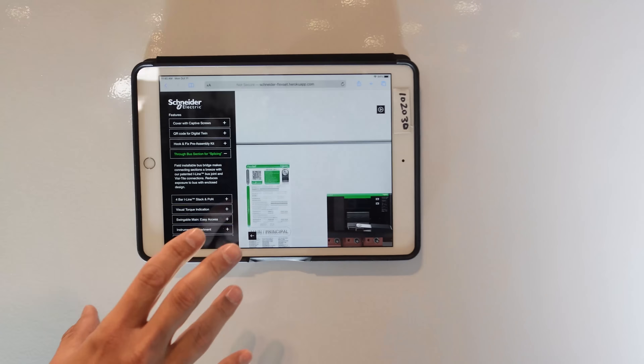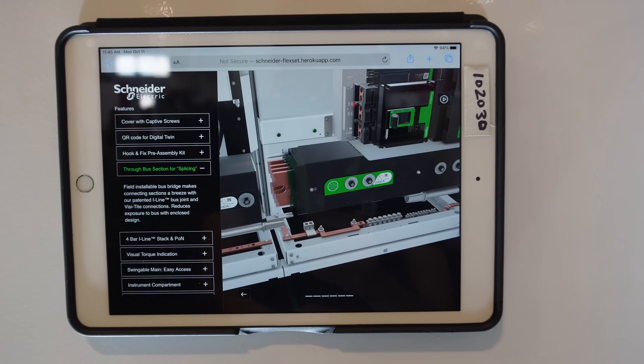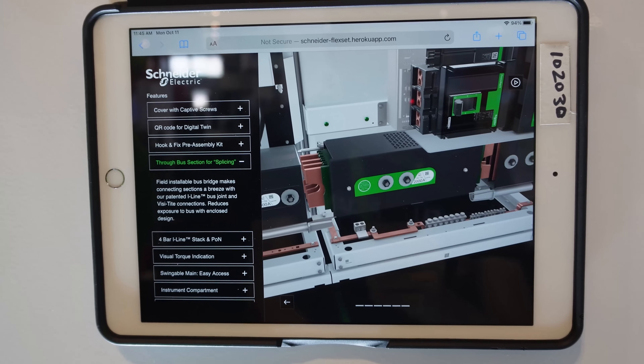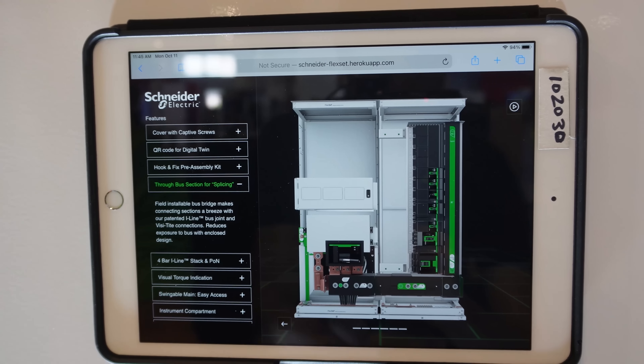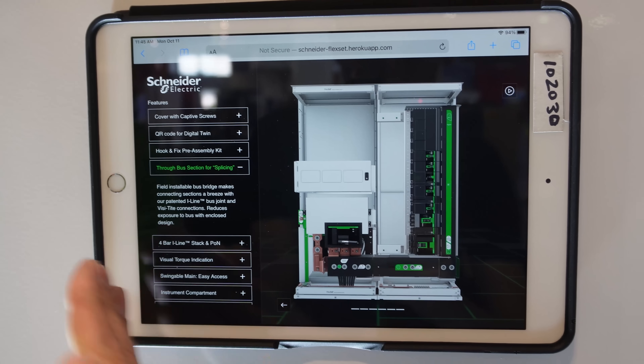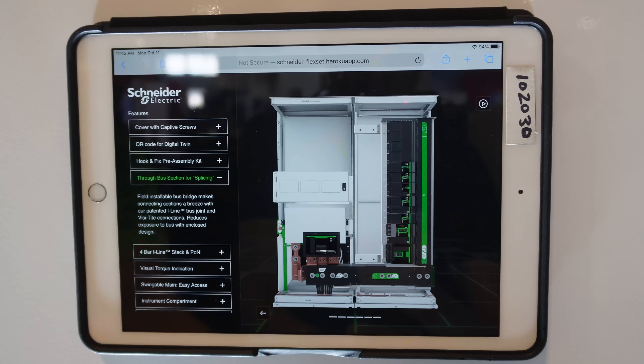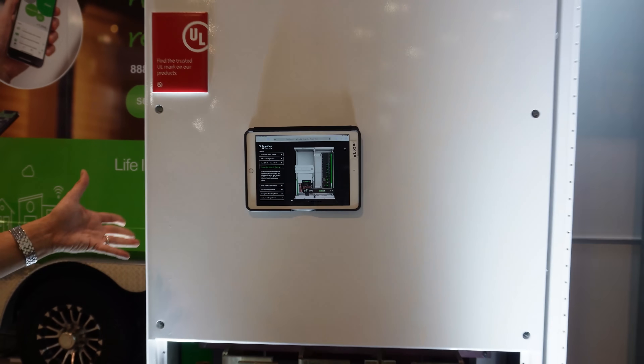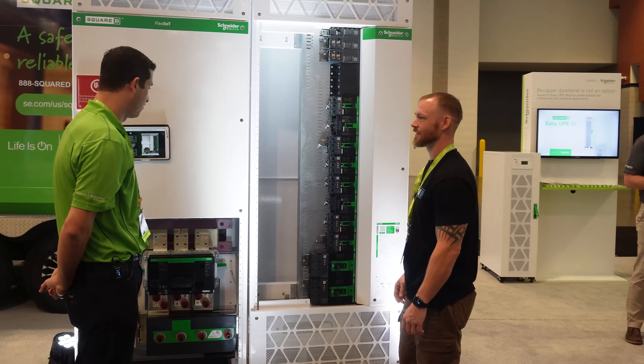This is a 3D model showing how the product works. Here's that part I described — see the telescoping bridge comes out. And then once you torque that, it basically connects both the load side of the main and feeds the feeder section so that the I-Line is now powered all in one move. That's great. So what usually takes a day or half a day to do all this splicing — it's now done in five minutes.